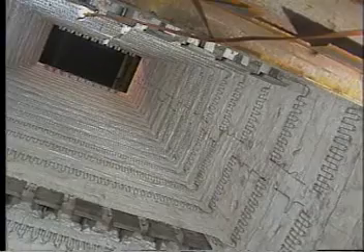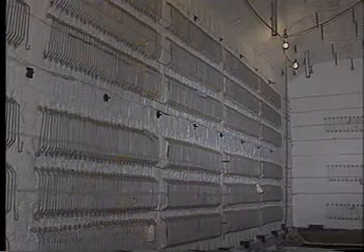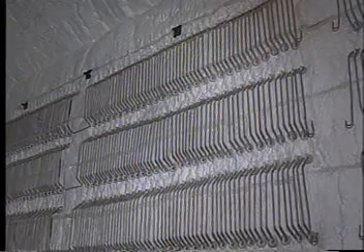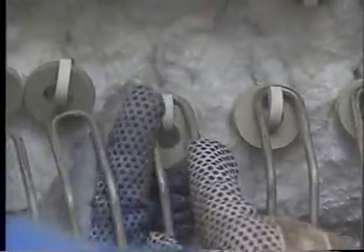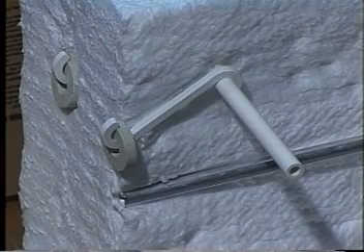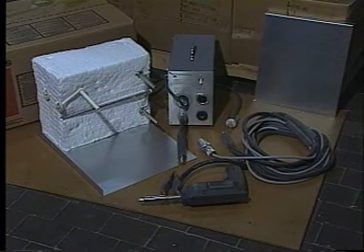Since 1977, the PyroBlock EES system has offered a patented method of supporting electric heating elements from PyroBlock Y modules. Electric heating elements precision engineered and designed to customer specifications extend away from the modules, maximizing heat radiation and temperature uniformity while offering extended, reliable service. Custom-formed rod overbend, ribbon, or coil heating elements are attached to the Y modules by ceramic or alloy hangers. The ceramic rods are embedded within the ceramic fiber Y module to ensure complete electric isolation and thermal insulation from the furnace shell.